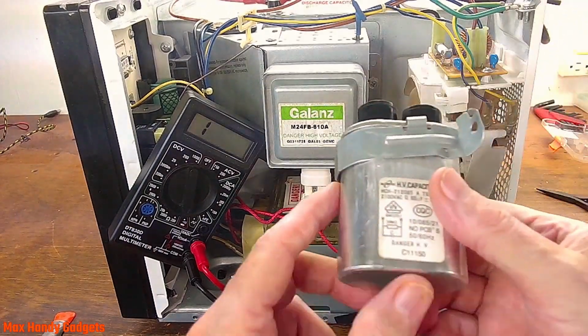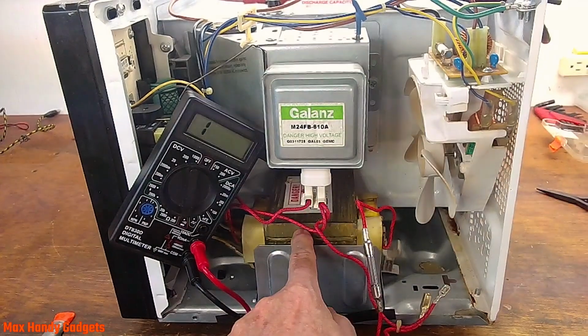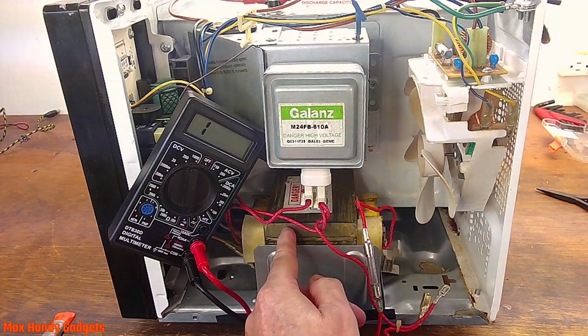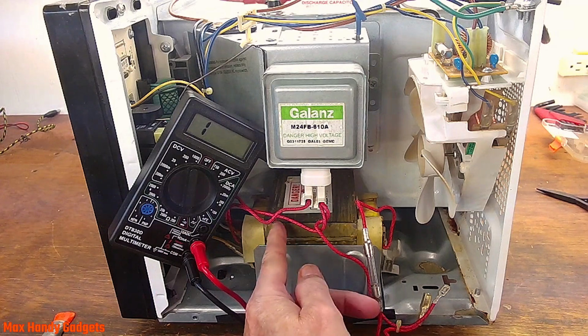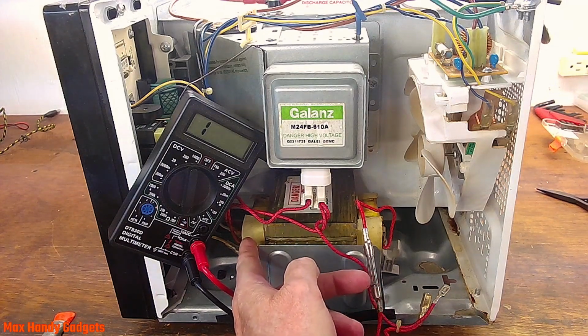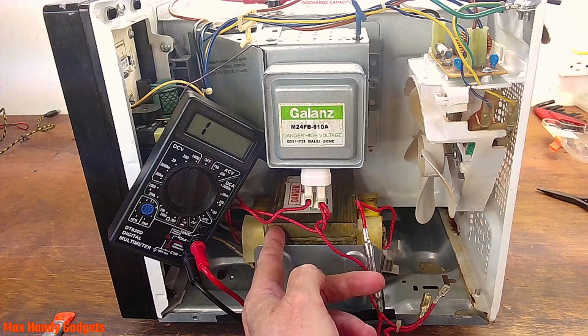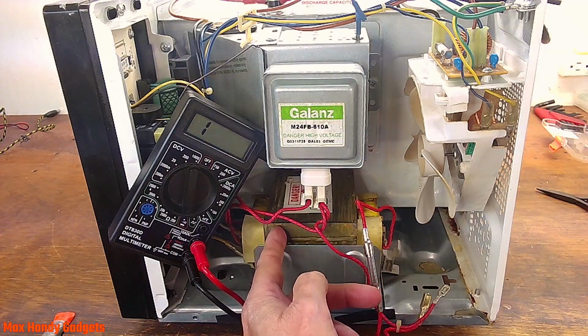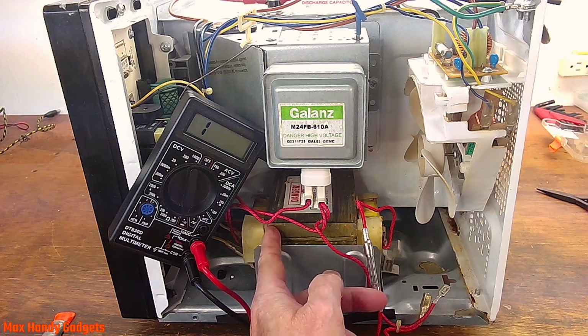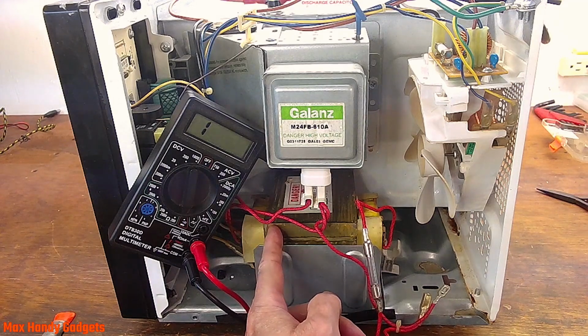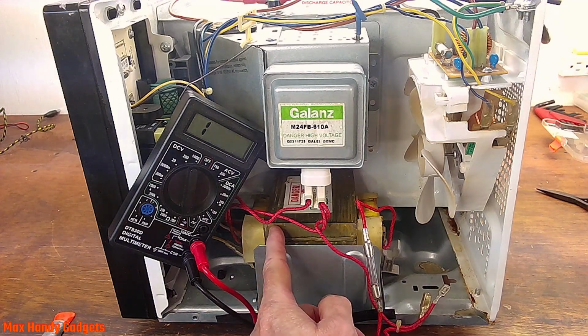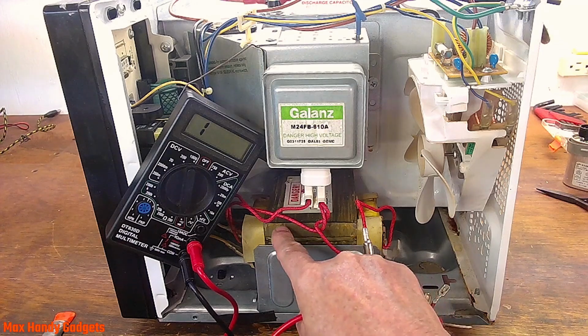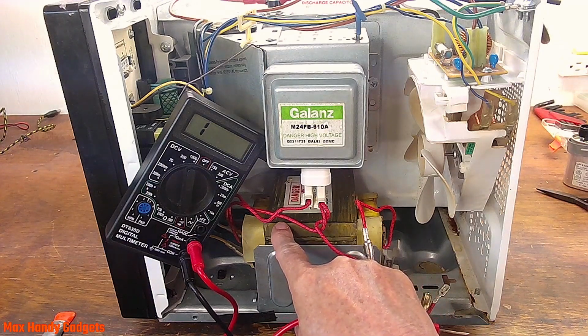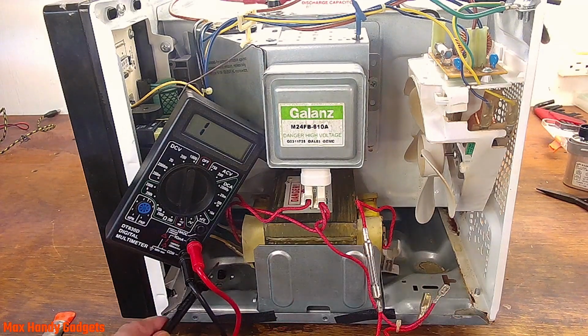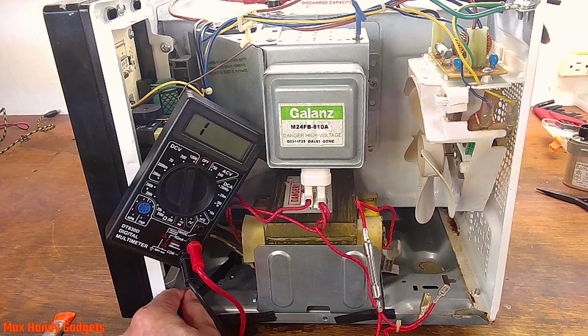Let's get the transformer out of here and check it out to see what happened to it. Maybe it's just right near the terminal end there where it might have hit ground or something like that. Let's go ahead and test the transformer one more time to make sure. Let's see if it's still shorted out. We'll put our probe in here.